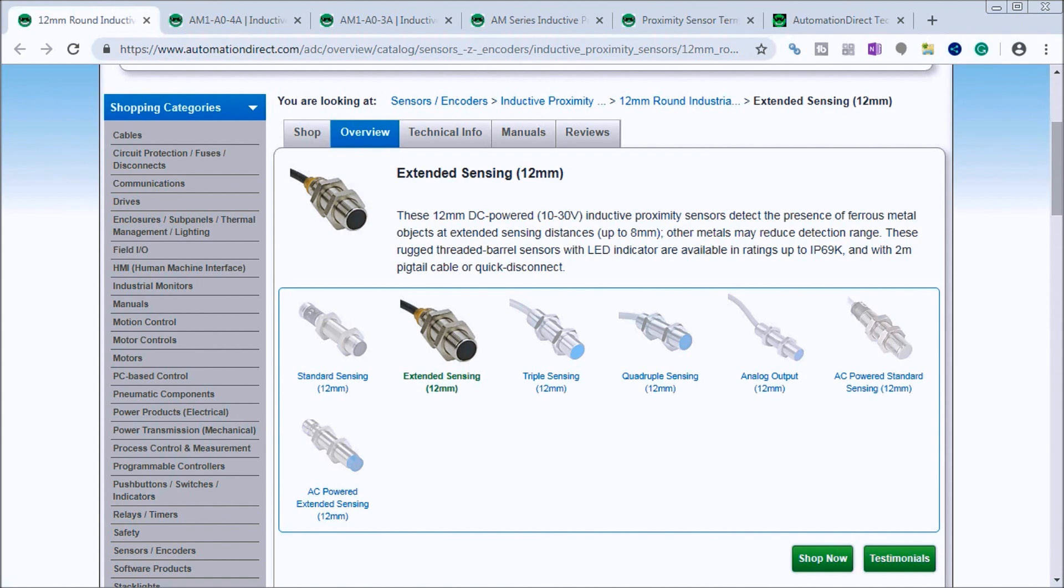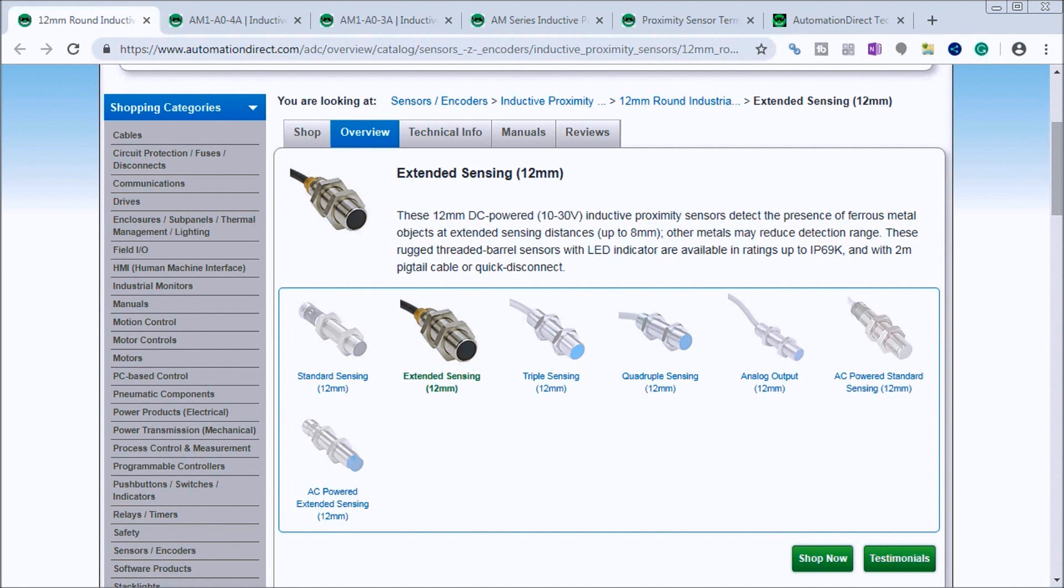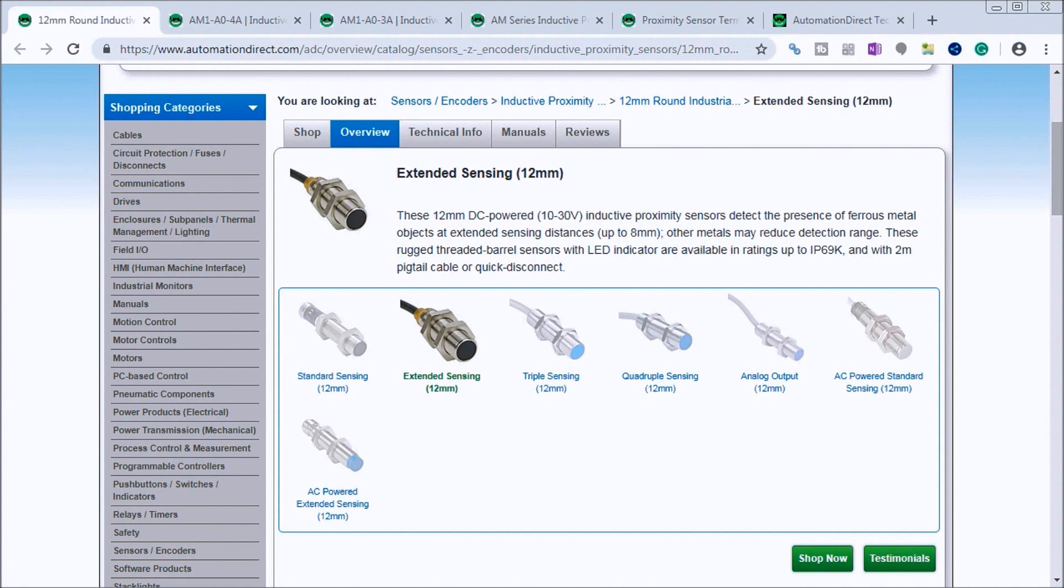Since there's no physical contact, there are no parts that will wear out and the life of the sensor is increased with less maintenance. The inductive proximity sensor will detect ferrous metals and the distance is usually specified in millimeters with steel. The sensor develops an electrical field when a metal or sensing object is introduced and it kills the oscillation circuit of the sensor, triggering the output.